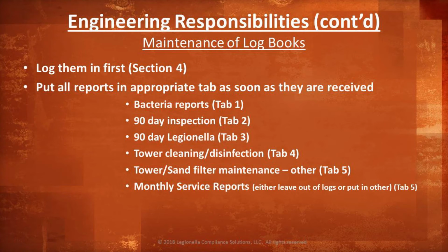You never know when the DOH is coming to inspect your system. These reports include bacteria test reports, 90-day compliance inspections, 90-day Legionella, any tower cleaning or disinfection, and any tower or sand filter maintenance. We also recommend placing your normal water treatment monthly service reports into a separate binder in order to avoid confusion or cause a problem by giving the DOH more information than they ask for.